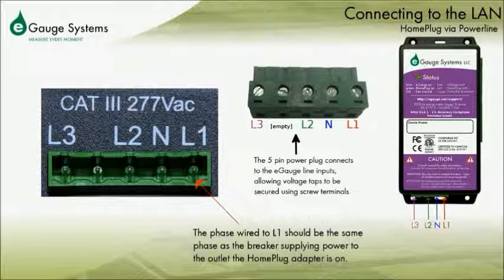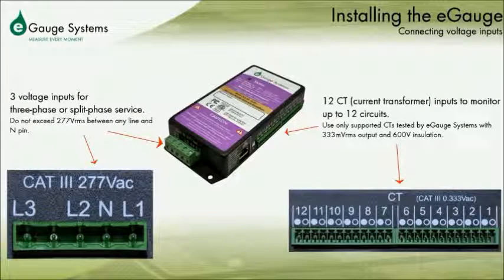Any phase can be wired into L1 of the eGauge, so if a certain outlet must be used for the home plug adapter, that phase can be wired into L1. After installing the home plug, you will want to install the eGauge main unit. The eGauge main unit has 3 voltage inputs and 12 CT inputs. Each phase of the electrical system being monitored will need to be wired into the separate voltage references.